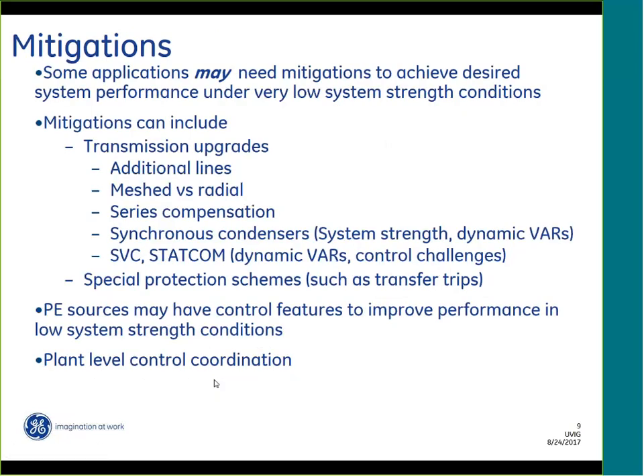So what are the mitigations? There are a large number of things that can be done to increase the system strength. In principle, the mitigations would include transmission upgrades like adding a line. Obviously, that's typically not desired, but in principle, if you add lines in parallel to the corridor that already exists, you will tend to increase the system strength.